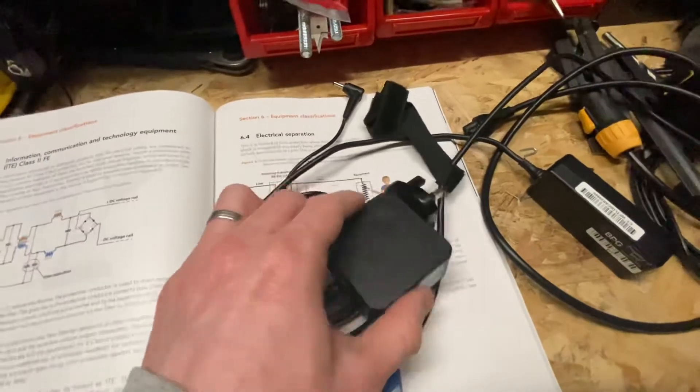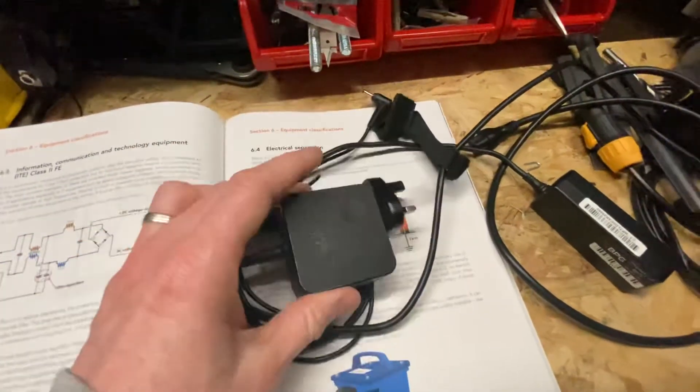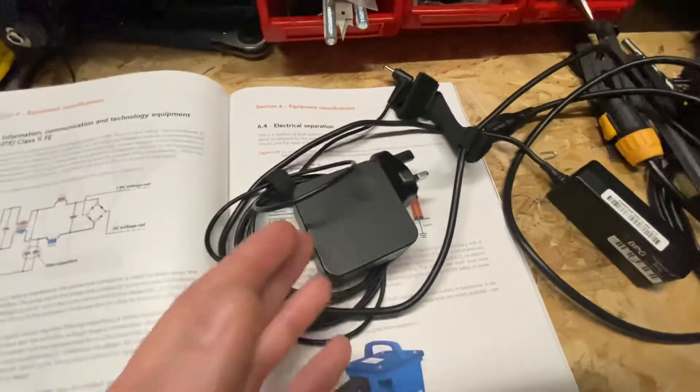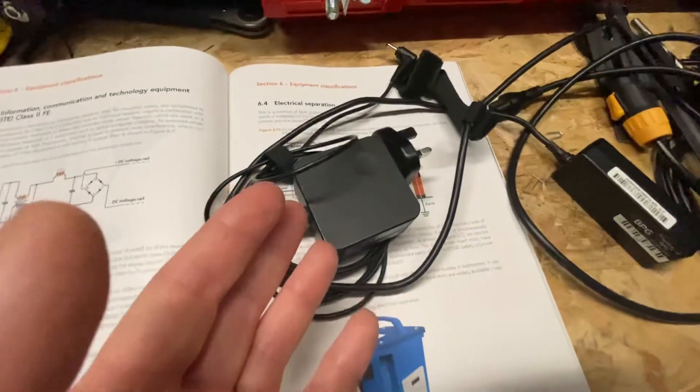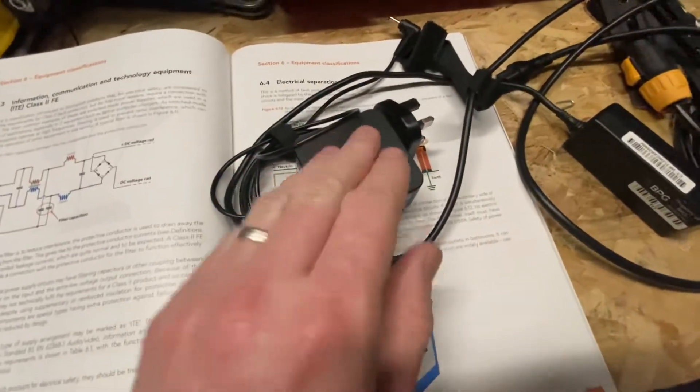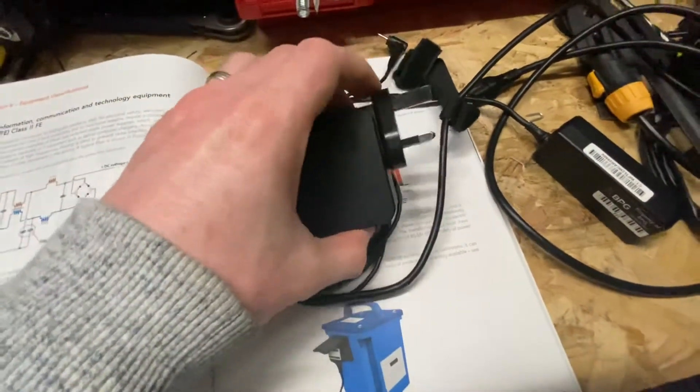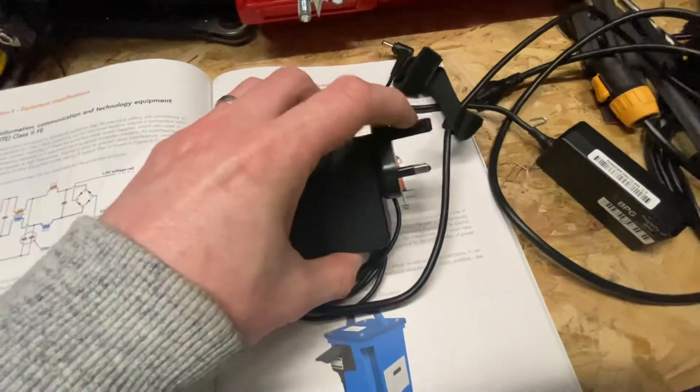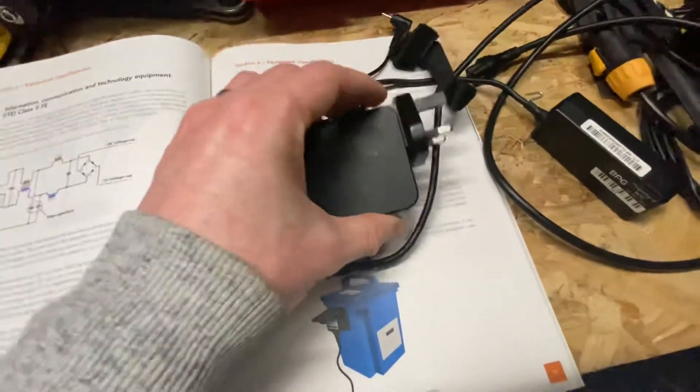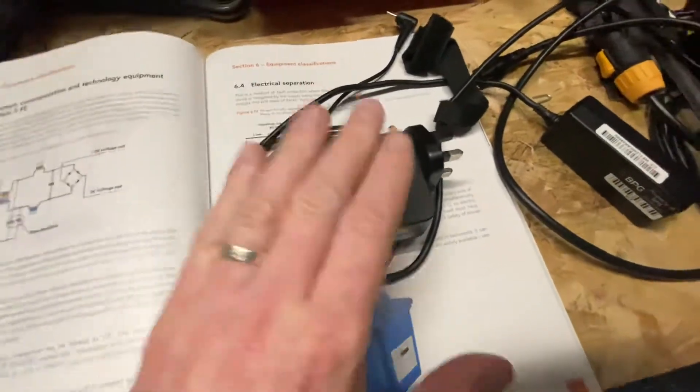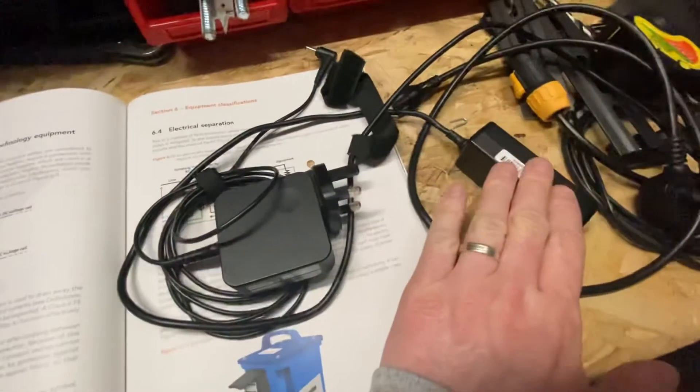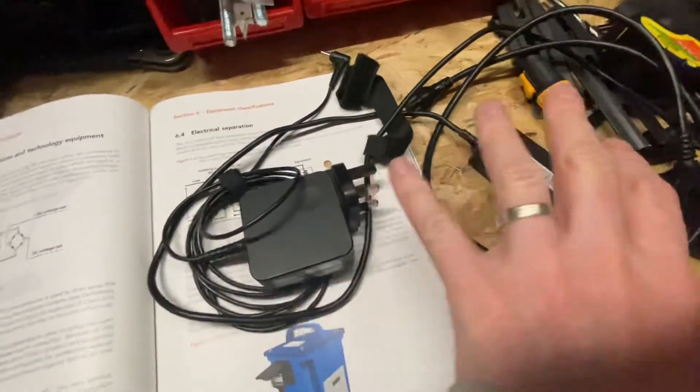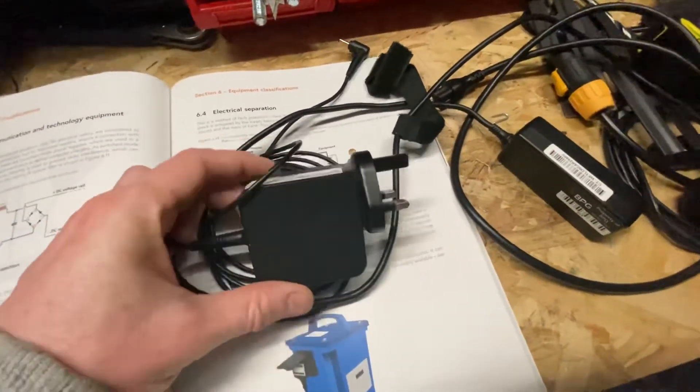But again, you would treat it as a class 2 appliance. I would do a visual check on this, check there's no signs of heat damage, check that the plastic pin is actually intact. Some of these may have a metal pin, so it may have a functional earth facility on it, but then you would treat it the same as one of these. They're both the same, just a different design.